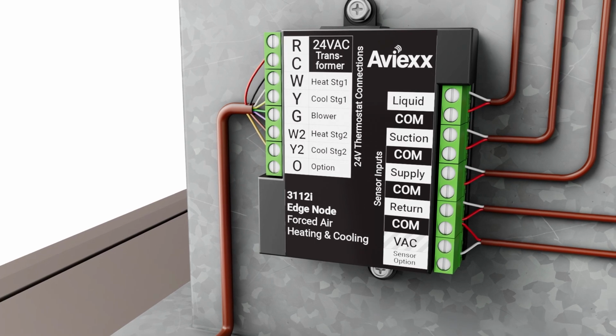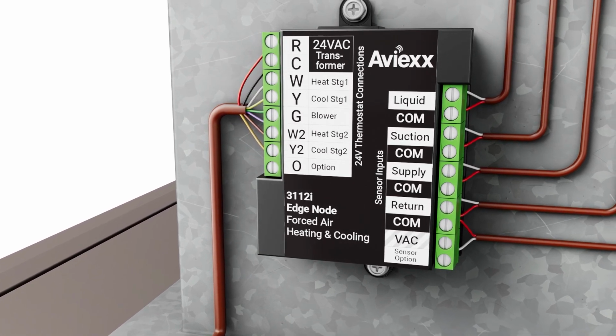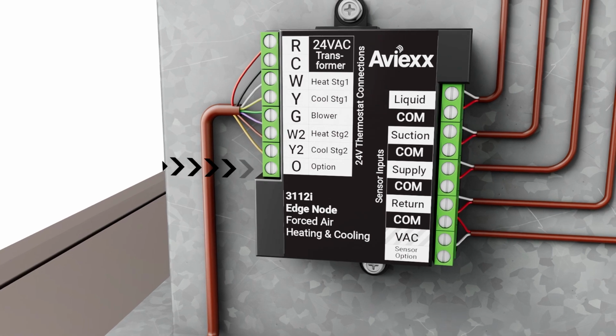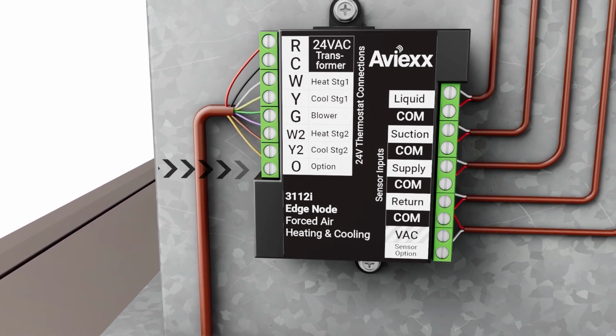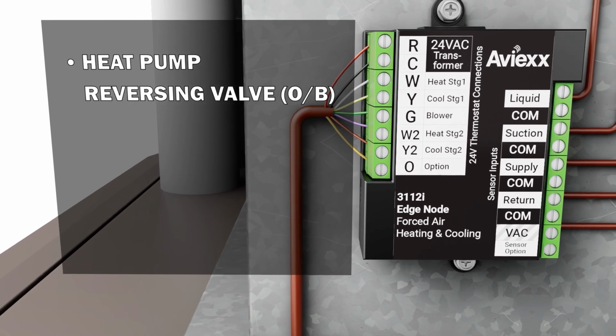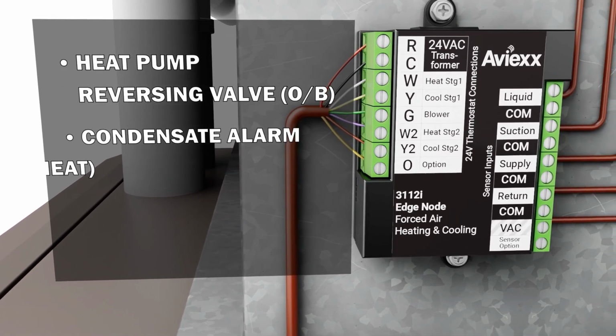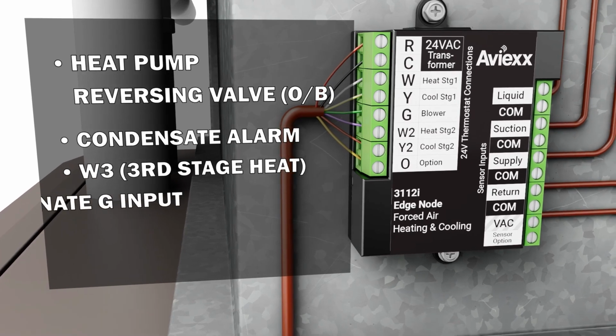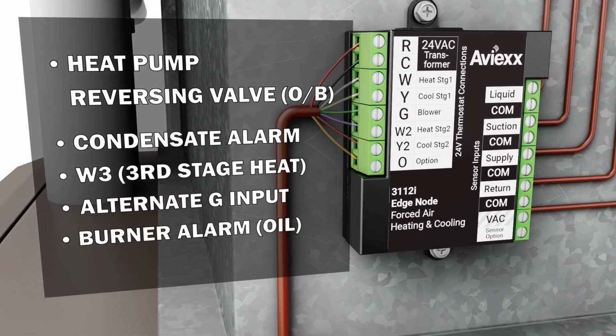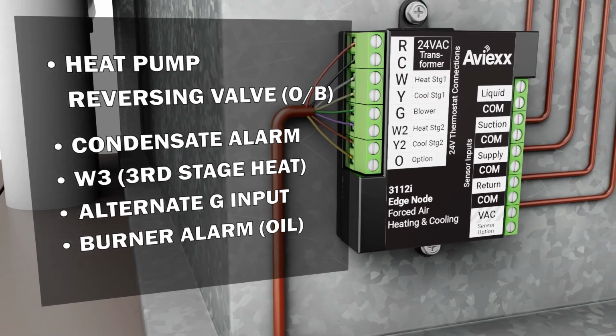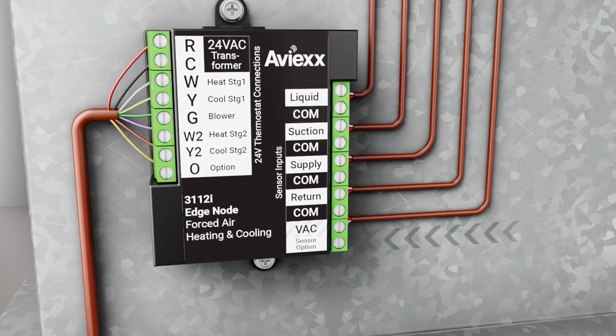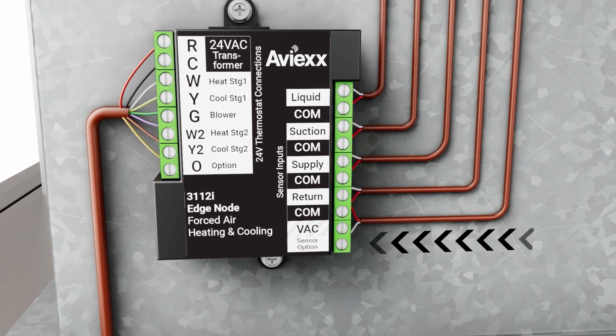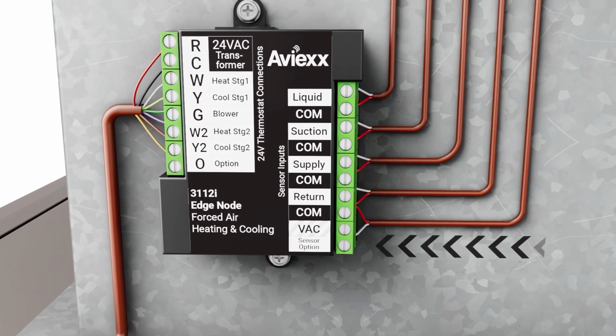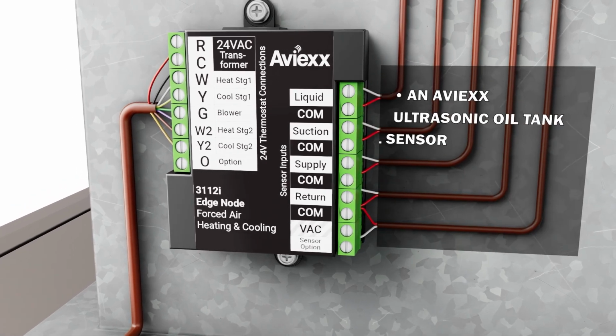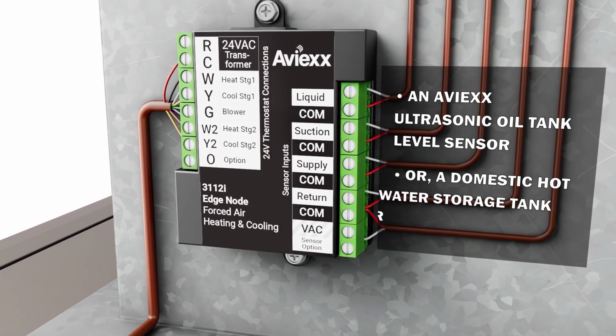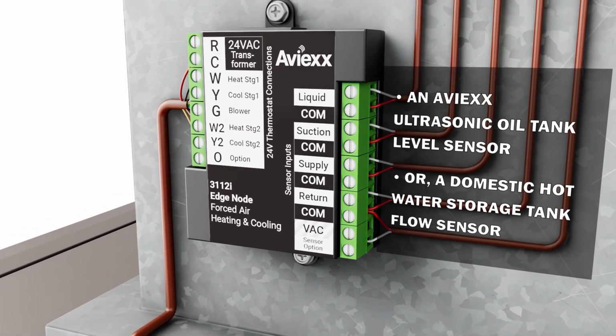Aviexx offers optional inputs. On the thermostat side of the Edge node, the terminal marked O can be used for a variety of inputs. Most commonly, it's used for heat pump reversing valve, condensate alarm, third stage of heating, an alternate location for the G wire, or burner alarms for oil burners. On the sensor side of the Edge node is the sensor option terminal, which allows for a variety of optional sensor inputs. Most commonly, an Aviexx ultrasonic oil tank level sensor or a domestic hot water storage tank flow sensor.